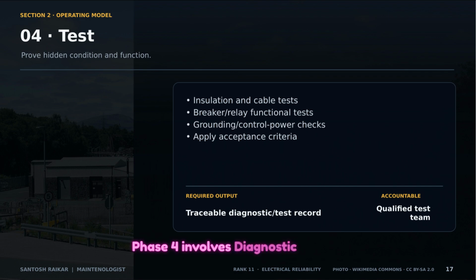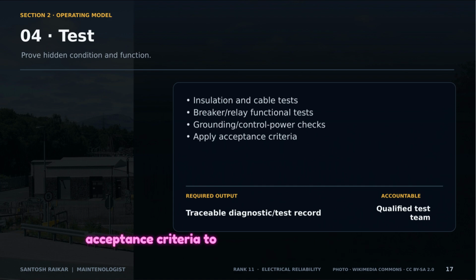Phase 4 involves diagnostic testing. This is where we prove the health of hidden components, like cable insulation and breaker functionality. Every test must be measured against defined acceptance criteria to create a traceable record of health.